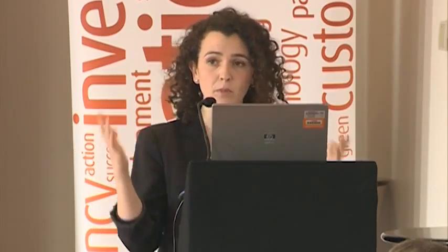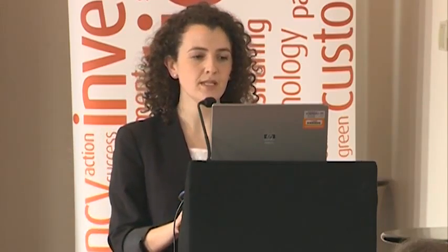So like that, we came up with this methodology of how to determine how many megawatts we think is a reasonable amount of megawatts to connect, where developers or generators would actually prefer the cost of curtailment to their cost of paying for the reinforcement. So we did this analysis and we came up with the numbers, and then we had the challenge of saying, okay, well now let's set up a set of rules so we can give these developers an offer. Essentially these generators have their business as usual alternative, which costs more than £1.2 million, and go connect a single sole use asset somewhere else in the network, or connect to FPP.